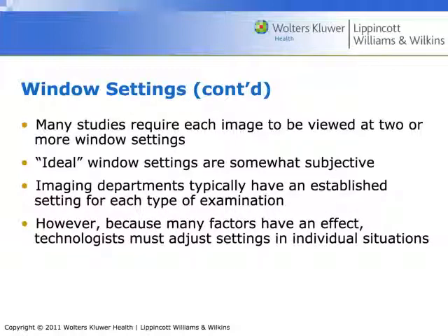Most studies require at least two different window settings. We'll do reconstructions of a series of lung windows and then a series of abdomen windows for just about everything we do. For a brain, we do a series of skull windows for the bony detail and a series for the white matter. Ideal window settings are kind of subjective — it depends on the viewer and the monitor. Image departments will have some preset window width and levels that are automatically generated by the CT scanner, and you can manipulate from there. Most CT scanners also have preset function keys at the top of the keyboard to quickly change the window width and level.